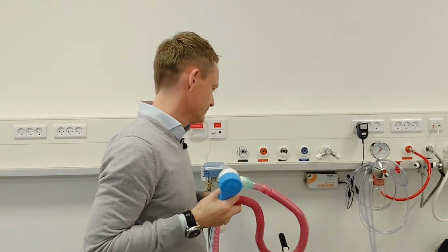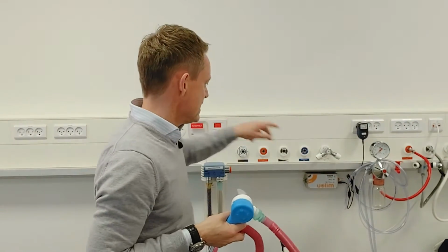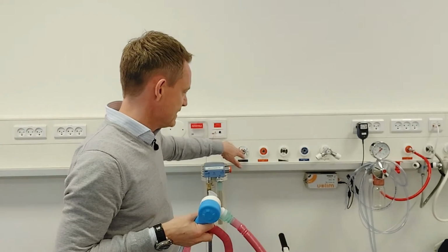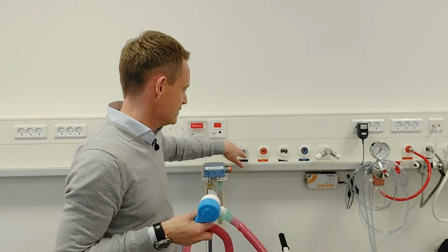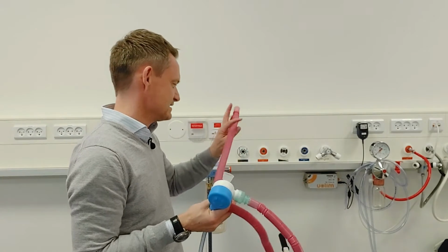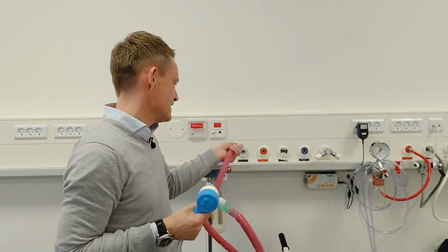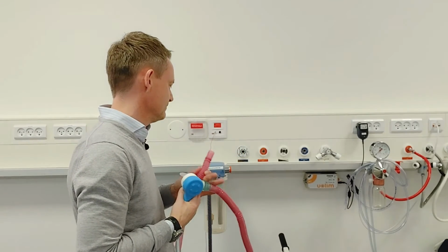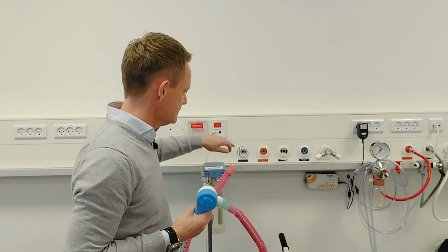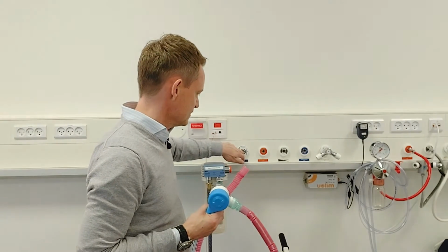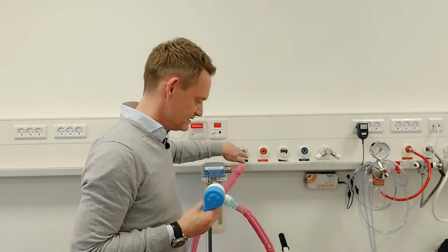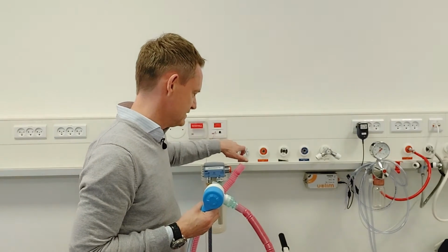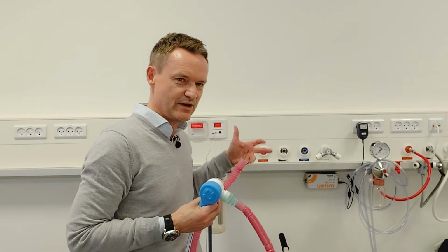In this hospital, they have an AGSS port. So this is the AGSS port. And what that means is that I now need to have all the expired gas going into that connection here. And what you see is that they don't fit. So I need to have a system in between where they fit. The system that they have in this hospital is an active AGSS system, meaning that as soon as I plug something into this system, it immediately generates vacuum.